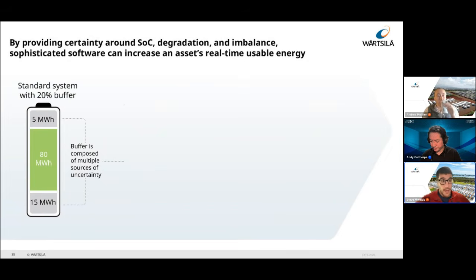Here we have a battery system on the left. It's about 100 megawatt hours, and the asset operator here is using on a day-by-day basis 80 megawatt hours, holding in buffer 20%, or roughly 20 megawatt hours. They're probably wanting to avoid the risk of making a bid into the market and then not being able to fulfill that at the bottom of their SoC range. If they were to bid 20 megawatt hours and then only had 10 left, they might have to cover that commitment in the real-time market, which has an uncertain financial cost.